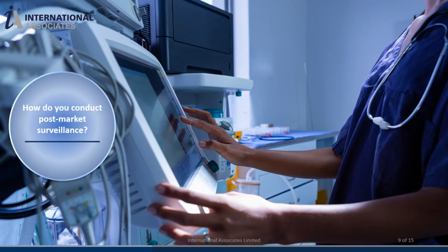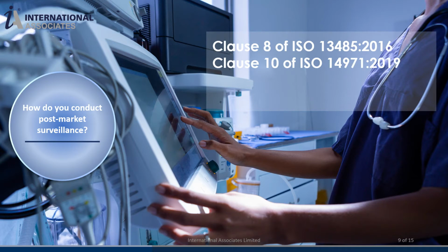So, how might you go about conducting post-market surveillance? Let us start by looking at the basic structure. According to Clause 8 of ISO 13485/2016, and Clause 10 of ISO 14971/2019, the manufacturer must document one or more processes for collecting and analyzing data from production and post-production activities. MDR Article 10.9 states that the manufacturer's quality management system must address the setup, implementation, and maintenance of a post-market surveillance system following Article 83. Therefore, it is necessary to prepare a documented procedure for post-market surveillance in which you will describe how your PMS system is organized.